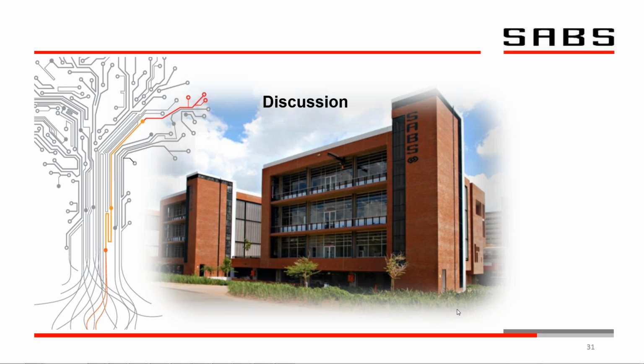So we had that specialist Gavin De Beer come along, and it's basically like advanced trim balancing on site. So he puts accelerometers and sensors on the system and a key phaser to reference the exact angle of the rotor at the time. And after a few test runs, he applies balancing weights in the same way you would balance the rotors in a balancing machine. And that's how we managed to get the vibration so low. So just the right skill with the right effort and meticulousness.